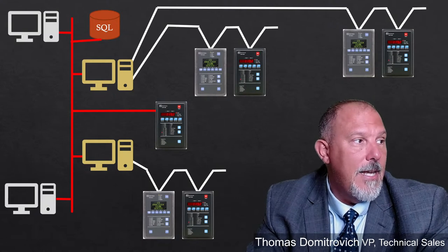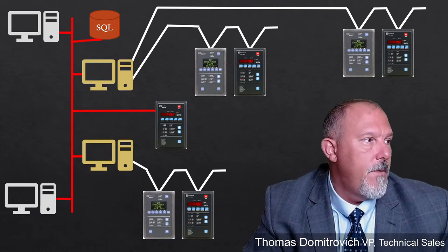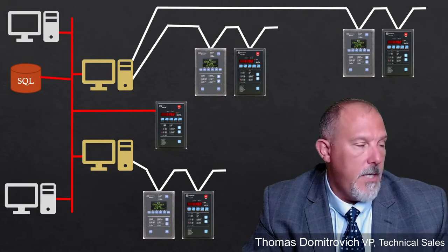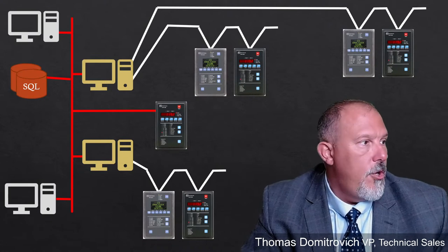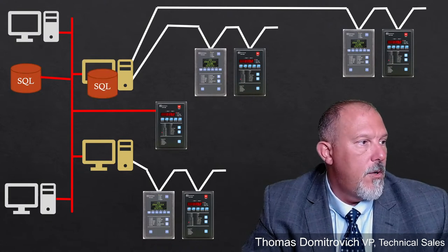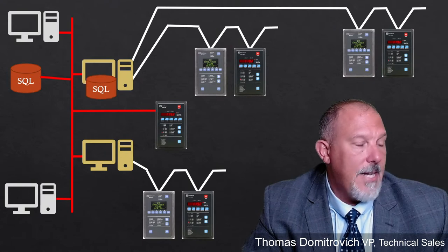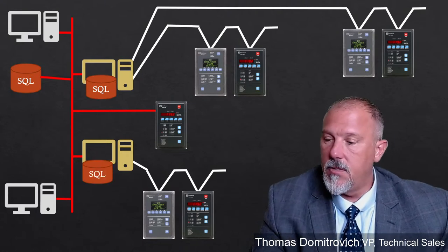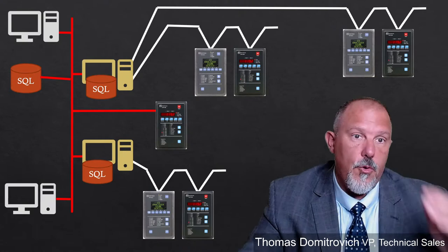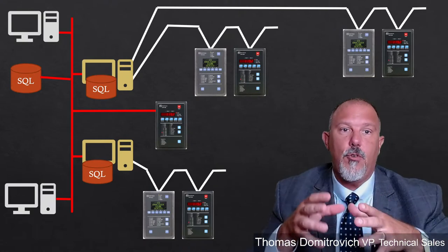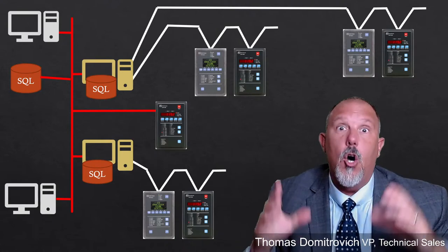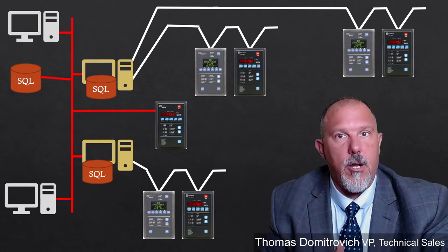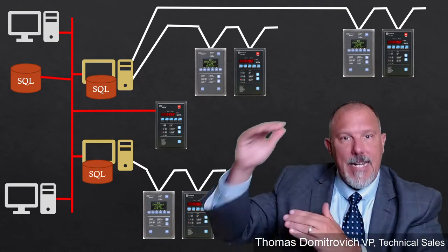So you might need to take an approach where you have a SQL server that is up there on the network, and you have SQL servers, databases locally on each of these systems. So in this case here, now you don't have the worry of, oh my gosh, my LAN is down, I'm missing energy data, because it's no longer logging to the SQL server. So you've got to think about the data that you're getting.